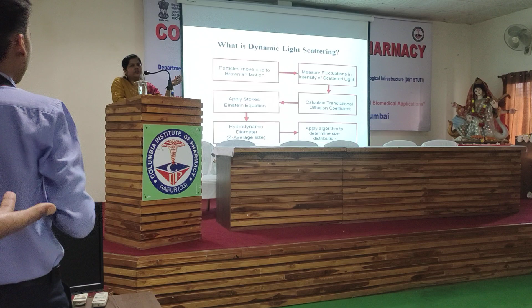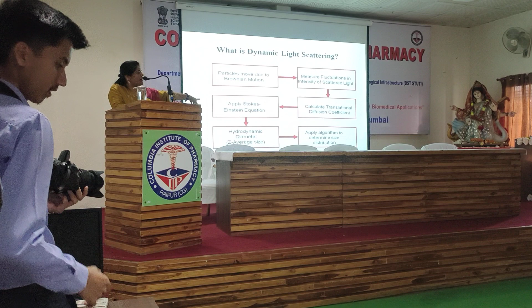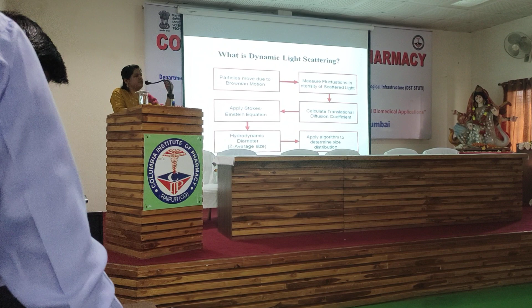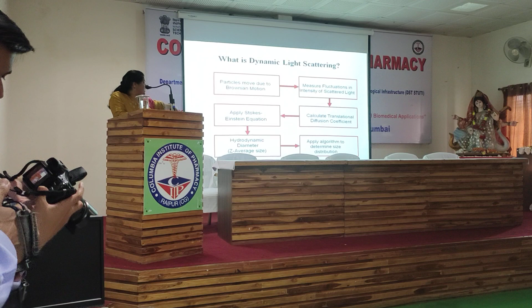When I show you the screen on the computer, you will see all these parameters, but our focus should be on this part, the hydrodynamic part. This is the region in which the particle size will be displayed in nanometers. And there are various methods for determining particle size. Our machine tells us the size directly in nanometers. In most machines, we do not get the direct output; then we have to apply an algorithm to convert it into nanometers or micrometers. But as far as our machine is concerned, we will get the result directly in nanometers, and that too under the heading of hydrodynamic diameter.